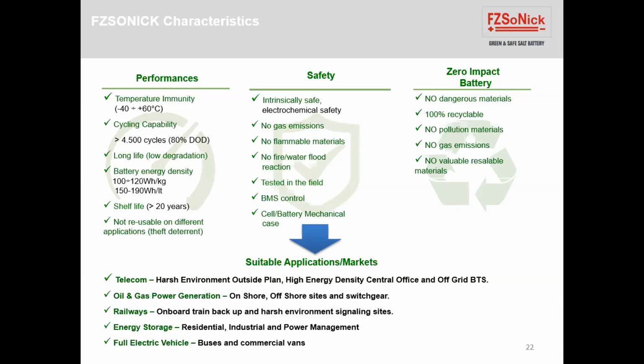The cycling capability depends on the application, but in stationary applications where cycling is well controlled, we have seen up to 4,500-5,000 cycles, with very low degradation as calendar life, and good energy density. Our shelf life with the battery in standby is more than 20 years - this is really not common, especially considering this can happen in ambients with very high temperatures.